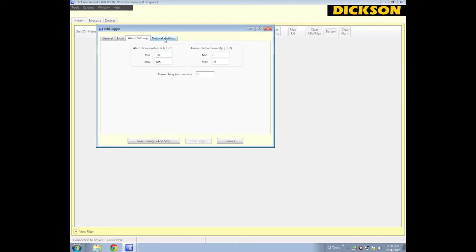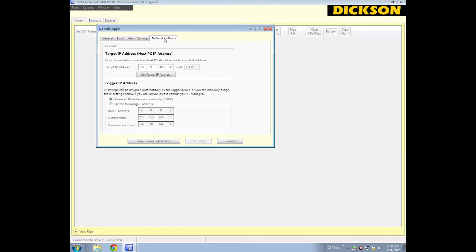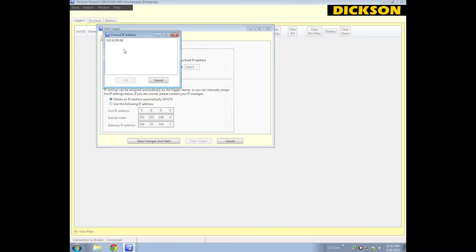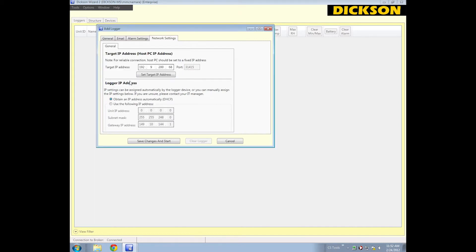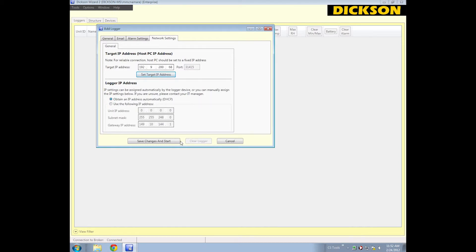The last step of the Ethernet logger is the Network Settings tab. You want to click Set Target IP Address. This is my computer's IP address, so you select that one and hit OK. If you need to set the logger's IP address, you can do that here, but most of the time you'll be good with leaving it as Obtain an IP Address Automatically via DHCP.